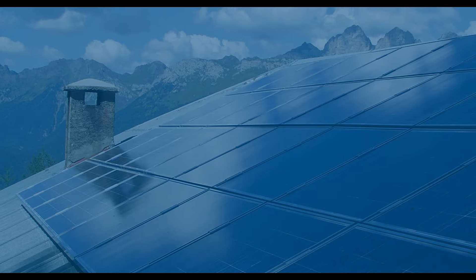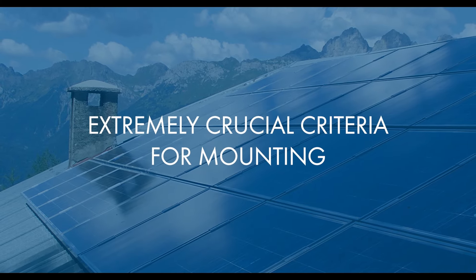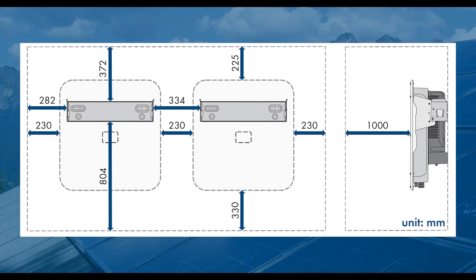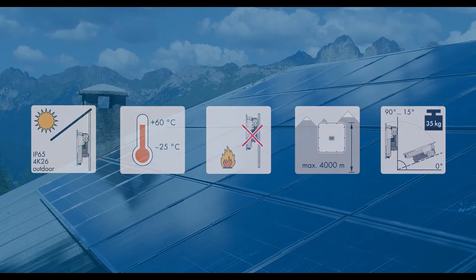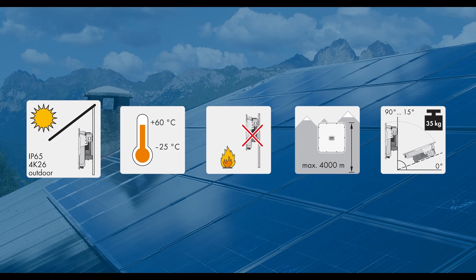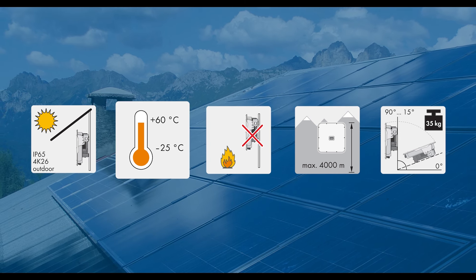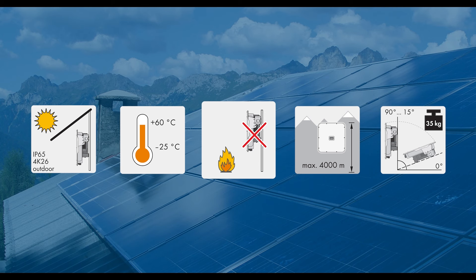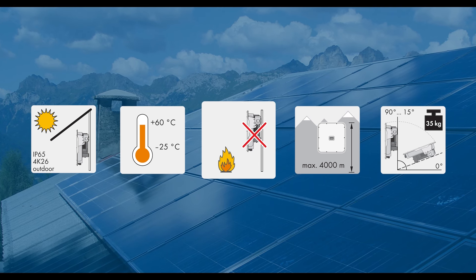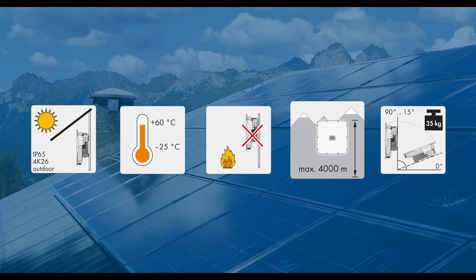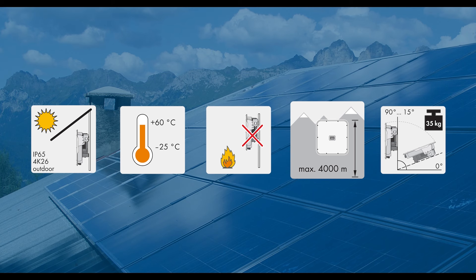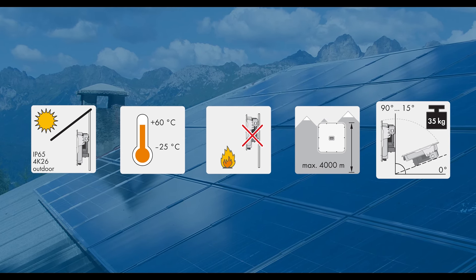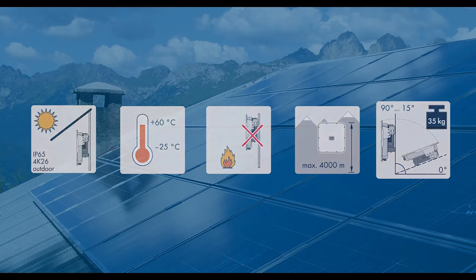Make a note of the following conditions as they are extremely crucial for mounting. Maintain recommended clearances to walls, inverter, or other objects. The inverter shouldn't be exposed to direct sunlight. All ambient conditions must be met. Do not mount the inverter in areas containing highly flammable materials or gases. Maximum permissible height limit from mean sea level is 4000 meters. Also maintain a minimum 15 degree incline in case of lying position.